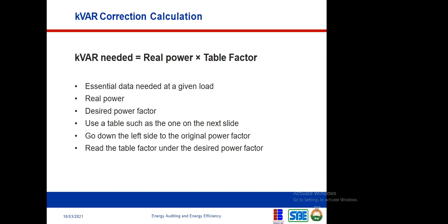This is a computational algorithm that has already been created by experts. You just look at your current power factor and the power factor that you want to achieve. So, let's go to the next table so I can demonstrate. This is a table of factors for correction of kVAR. kVAR is a waste that causes poor power factor.